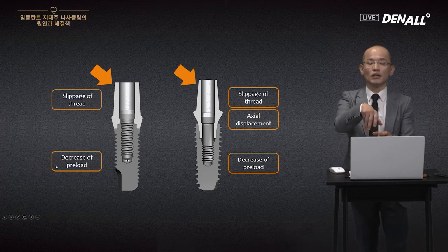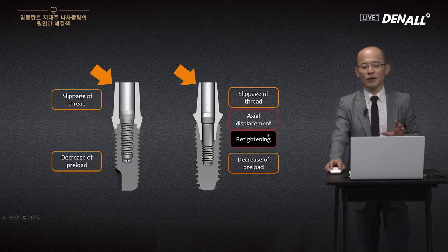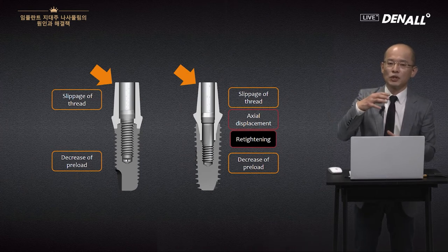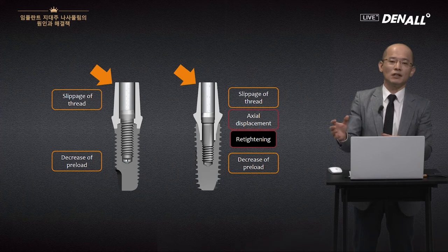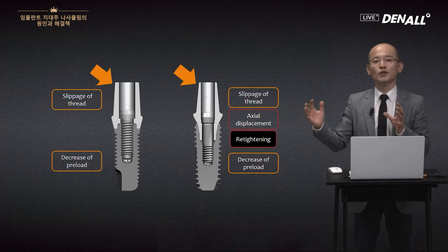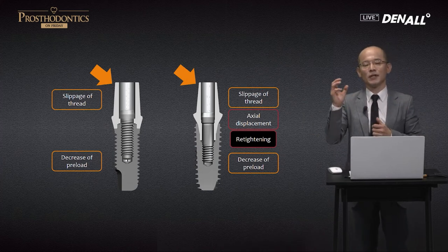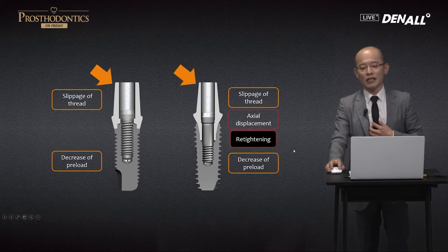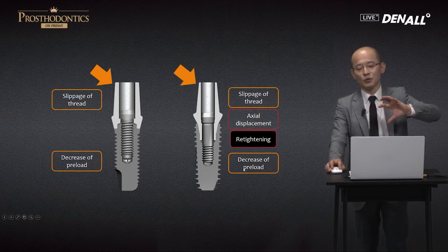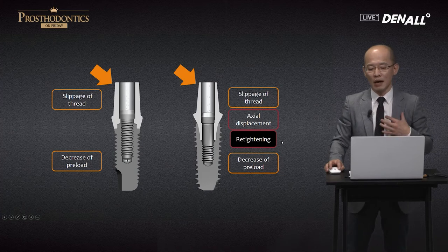Between the threads, there is settling effect and slippage, and the preload inevitably goes down — preload goes down. Because of the settling effect, it's always lower. But in this case, there's also re-tightening required for the internal type. Because of axial displacement, if you tighten once — depending on the surgeon, some say do it five minutes later, after four times do it again — what is important is that if there is axial displacement, one tightening is not enough to control this. To minimize the decrease of preload, the internal type must have a re-tightening step compared to the external type.